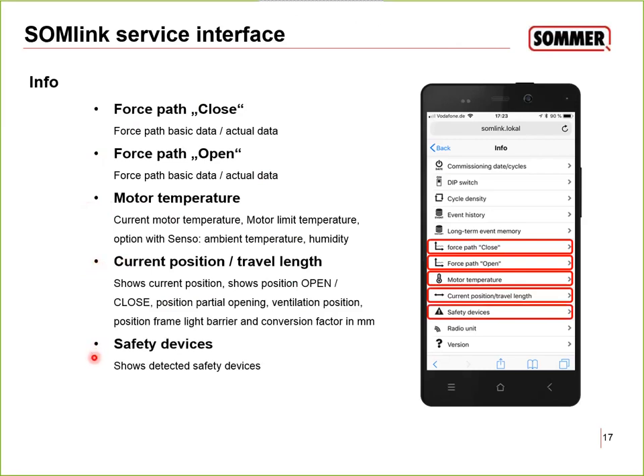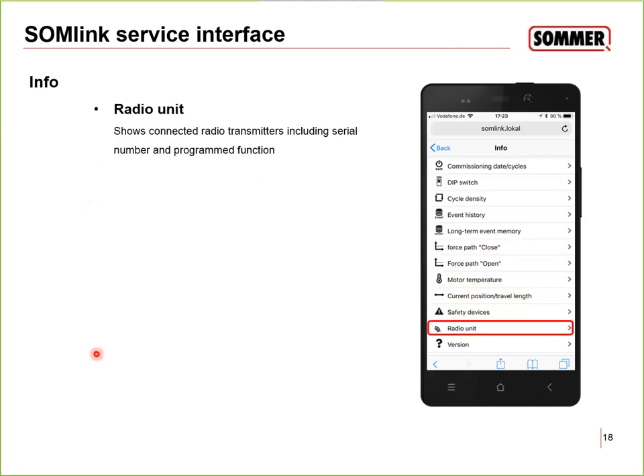You can read out what safety devices are connected. So it shows you if there is a photocell connected, or if there is a safety edge connected, or both. So you can see this over here. Next step is the radio unit. So it shows you all the transmitters, including the serial number and the program function. So you know, on the back side of the transmitter there is a serial number, and this is unique. Every transmitter got its own one, and so you know exactly which transmitter is coded in here. You can check it. You see all what's in the radio system.